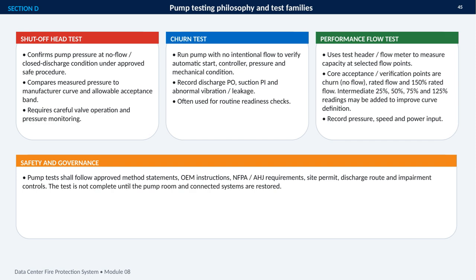During the test, we record discharge and suction pressure, along with any unusual vibration or leakage. The performance flow test measures capacity at selected flow points through a test header or flow meter. The key points are churn, rated flow, and 150% of rated flow, with intermediate readings added when a more complete curve is needed. We also record pressure, speed, and power input. Most importantly, every test must follow the approved method, OEM instructions, NFPA and AHJ requirements, permits, discharge planning, and impairment controls. The work is complete only after the pump room and connected systems are safely restored.